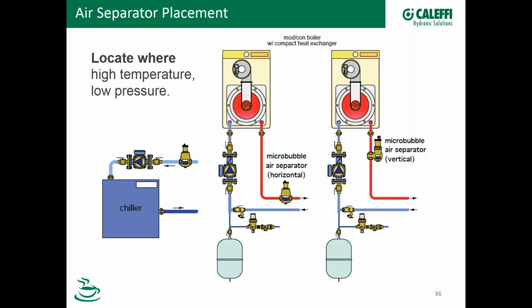Hey, Kevin, another question came in here on this particular slide. Before you leave, sorry about that. Yeah, no problem. On the chiller application, there we don't show an expansion tank. Now, ideally, you're going to have an expansion tank on a chilled water system, just as you would on a heating system. And as you would in a heating system, you always have your expansion tank placed upstream from your pump. You want to pump away from your expansion tank no matter what. So you would put it on the suction side as you would on the heating side. Okay, good. Great questions.